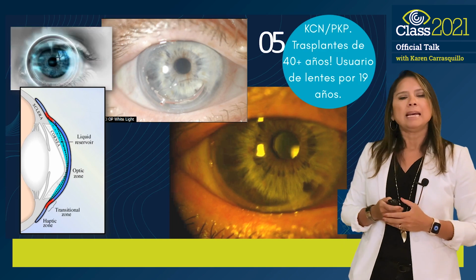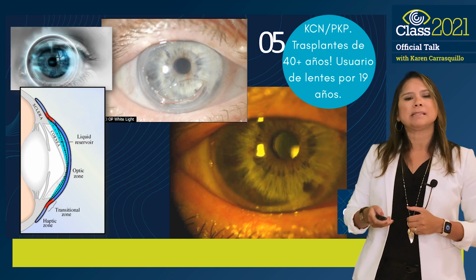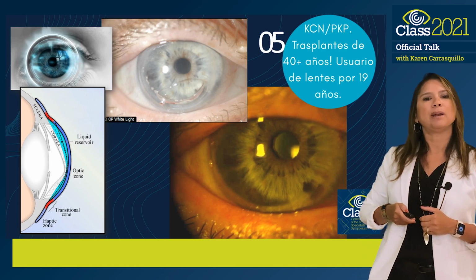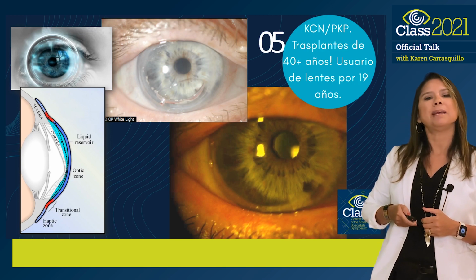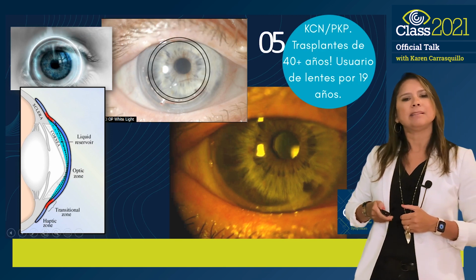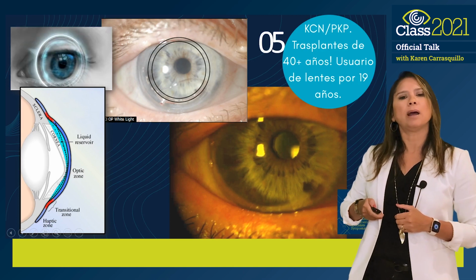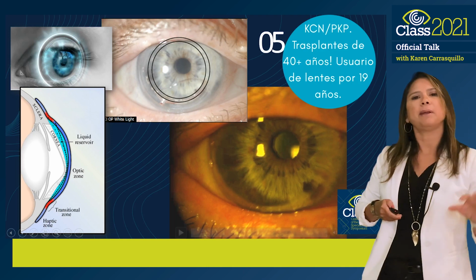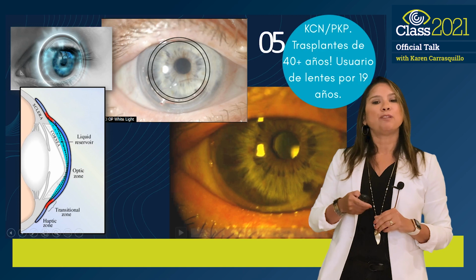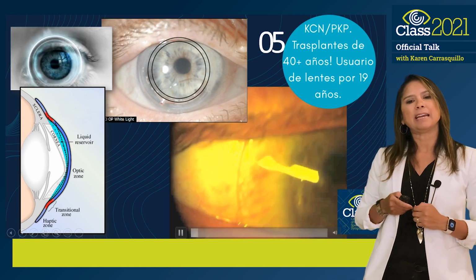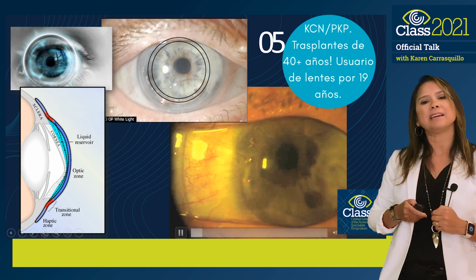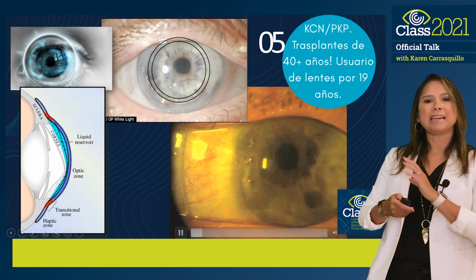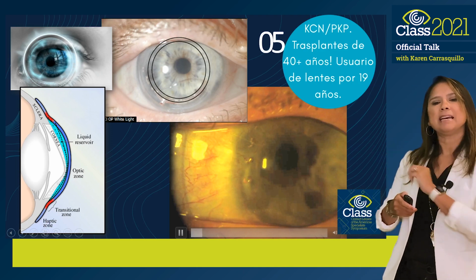So, we thought, what if I design a channel, but in this case, not in the haptic zone but in the optic zone, and I design it in a circumferential way, and I add fenestrations to it along that channel? Can I limit those bubbles to staying on that periphery? Well, that is what we did, and notice here in this video how the bubbles are starting to get much smaller, where we are really limiting them to that edge on the periphery, right?